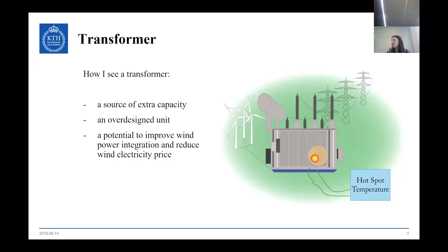What we'll speak of is dynamic transformer rating. It's based on using information from the transformer specification, also ambient parameters such as weather, ambient temperature and wind speed, and load parameters, in order to figure out the capacity limit of the power component at each time step. It's all based on the hotspot temperature, determined by running thermal models for transformer insulation. Normally you would like to keep it around 110 degrees Celsius in order to make sure that you don't exceed your projected lifetime.